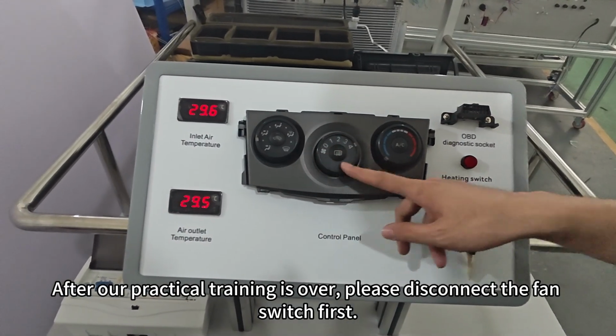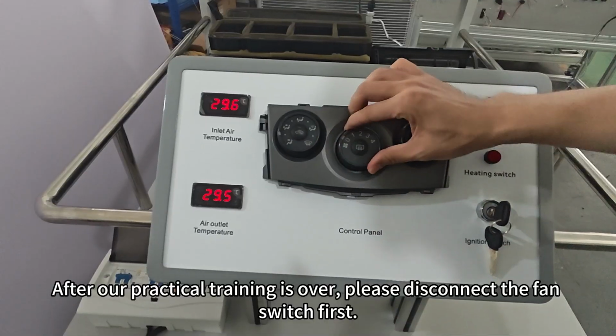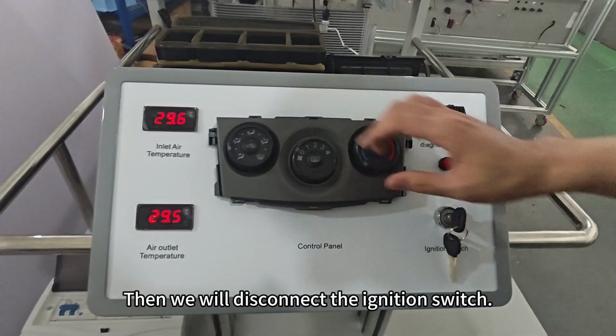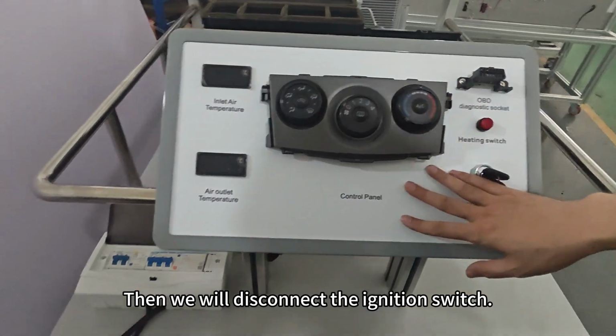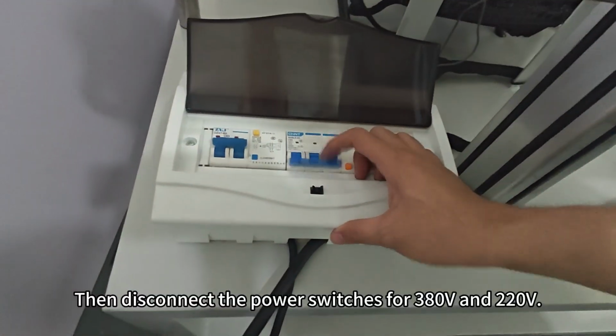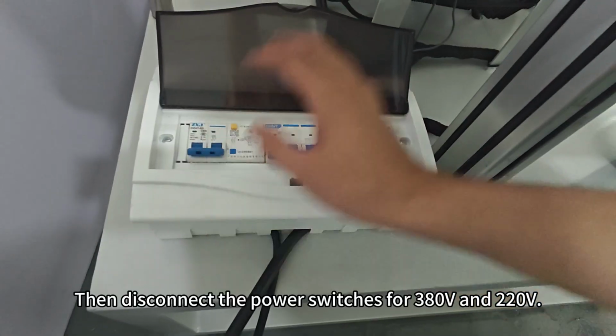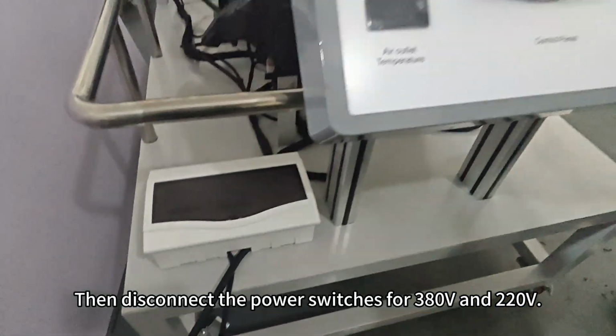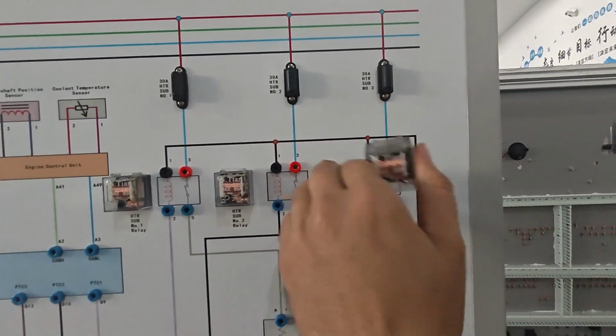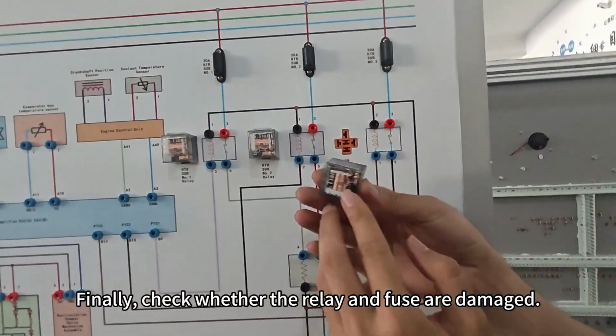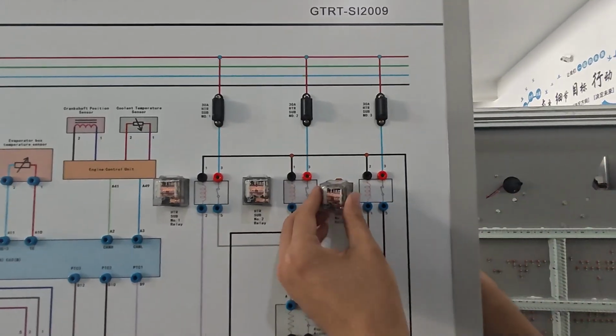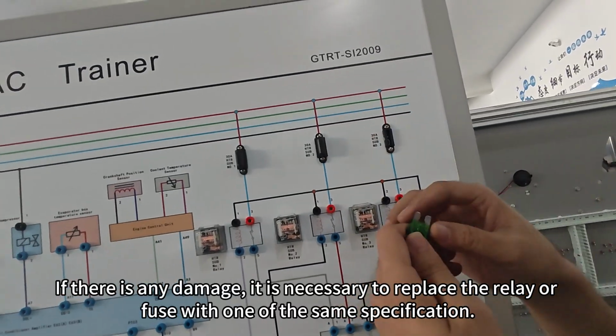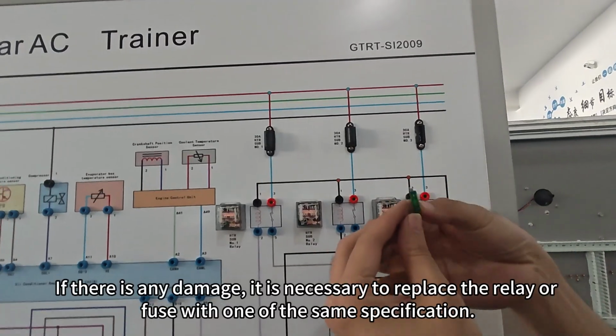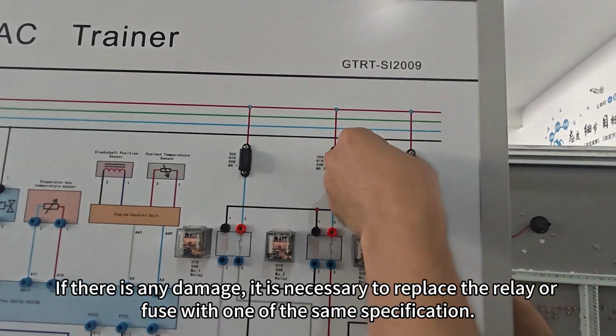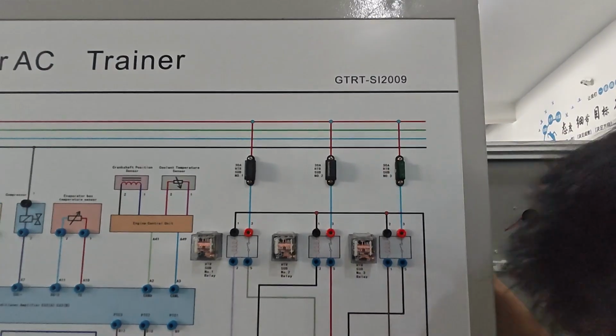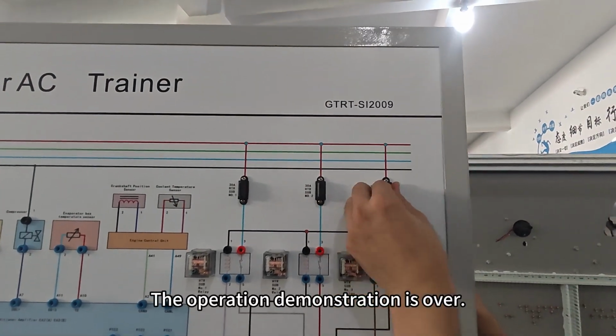After our practical training is over, please disconnect the fan switch first. Then we will disconnect the ignition switch. Then disconnect the power switches for 380 volts and 220 volts. Finally, check whether the relay and fuse are damaged. If there is any damage, it is necessary to replace the relay or fuse with one of the same specification. The operation demonstration is over.